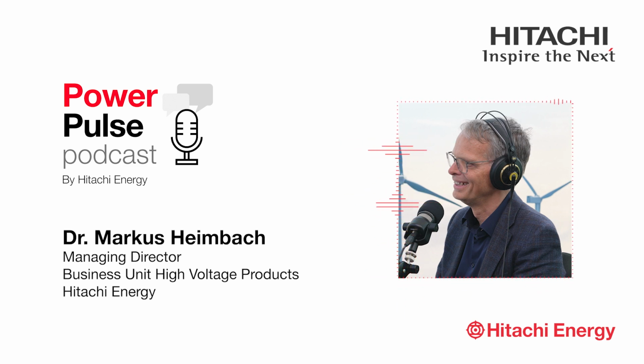Why is that? Because, a little bit technical now, a transmission line behaves somehow as a capacitor. And a capacitor means you are charging it and unloading it, which is not a big problem, but it's a problem because this current overlays the current which is used to transmit the power. And this current is then in the transmission system creating an additional loss.